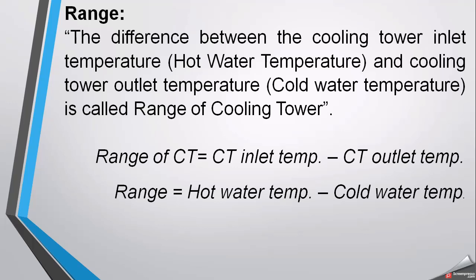Range is the difference between the cooling tower inlet temperature, which is the hot water, and the cooling tower outlet temperature, which is the cold water coming out. Range of cooling tower equals cooling tower inlet temperature minus cooling tower outlet temperature — or hot water temperature minus cold water temperature. This temperature difference is defined as the range.